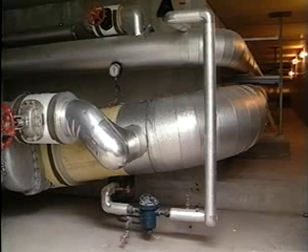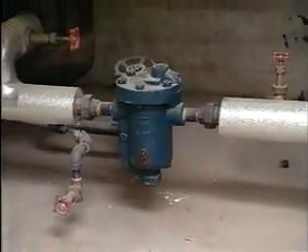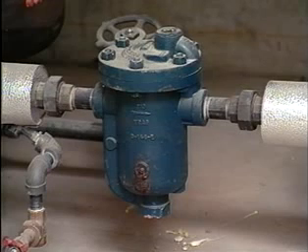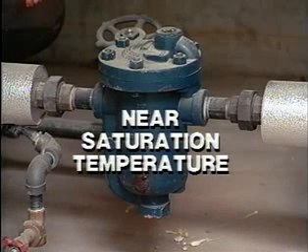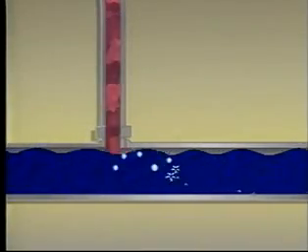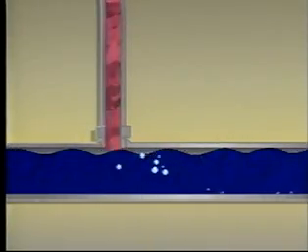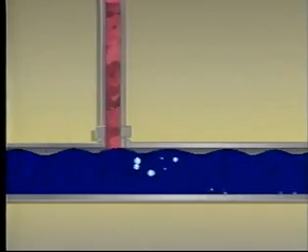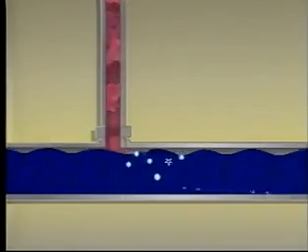One likely place for thermal shock to occur is in steam utility corridors. In these areas, the drip traps from high-pressure steam mains often discharge directly into the pumped condensate return lines. The temperature of the condensate in these lines usually ranges from 140 to 180 degrees Fahrenheit. The condensate being discharged from the steam trap is at nearly steam temperature when it passes through the trap orifice. When the trap discharge enters the low-pressure condensate line, a great deal of it flashes back into steam. The flash steam immediately collapses again when it encounters the relatively cool pump discharge water. This thermal shock often causes damaging water hammer.